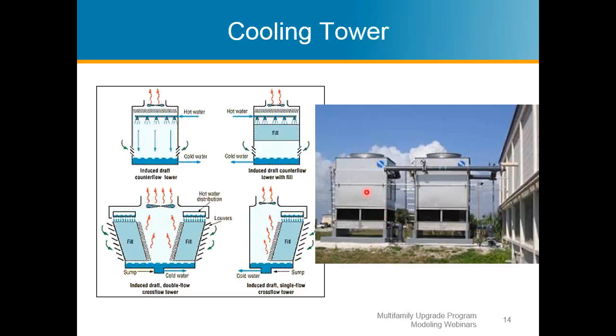Image on the right, this is what's called a cooling tower cell. You see in the industry, that's what they call these. They call them cells. You can have multiple cells depending on the load you need, and there are a couple of different ways of these cells being configured. It's a pretty simple concept. The hot water comes through the top inlet and is dispersed over what's called the fill. There's a bunch of fins that spread that water out so it removes the heat more effectively. Then a big impeller fan at the top helps drive outside air, which is colder than your hot water, through the fill, and it removes the heat from the water.